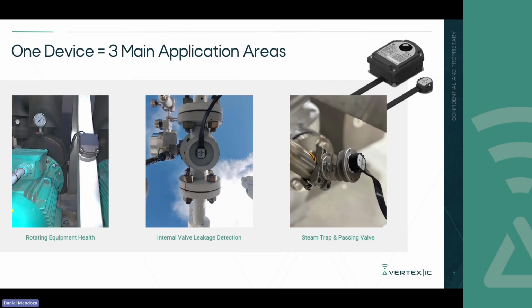This extends to internal leak detection, where whenever utilizing an ultrasound sensor, you could be able to tell if a valve is fully open or fully closed, and if you have any leaks coming through that valve. And then all the way through steam trap monitoring as well, where we're utilizing an ultrasound sensor to be able to listen if any steam leaks are happening in that steam trap.